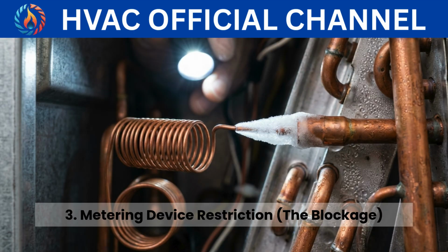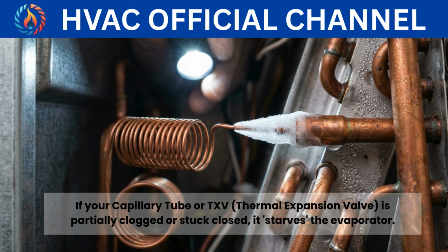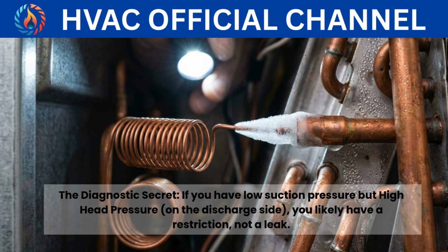3. Metering device restriction, the blockage. If your capillary tube or TXV, thermal expansion valve, is partially clogged or stuck closed, it starves the evaporator. The diagnostic secret: if you have low suction pressure but high head pressure on the discharge side, you likely have a restriction, not a leak.